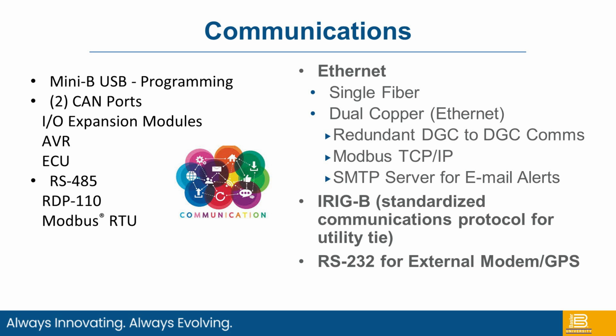So on board, we've got a USB mini B for programming. There are 2 CAN ports. Those CAN ports can be used for I/O expansion modules, voltage regulators, or electronic engines. We also have RS-485, which you'll see later as I show some of the accessories, the remote display panel, which is required for NFPA 110, and then the capability of using Modbus RTU to speak with building management systems as needed. There are also Ethernet ports too, and they can be either a single fiber or a dual copper option.